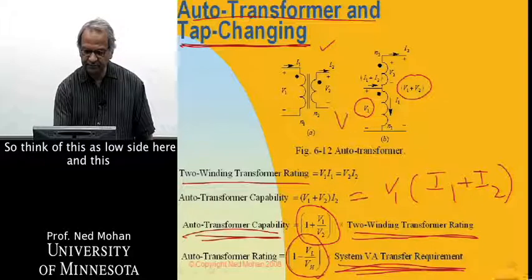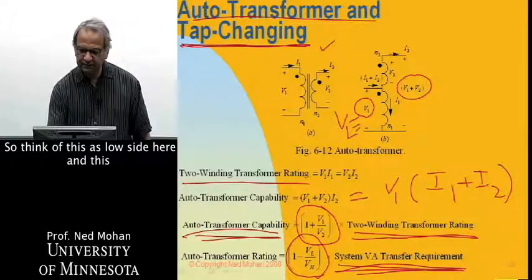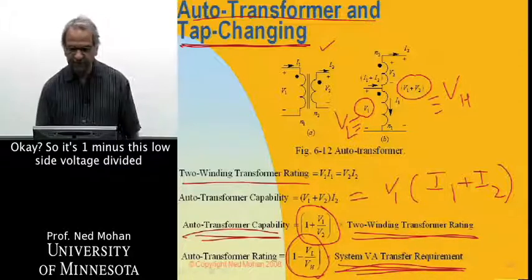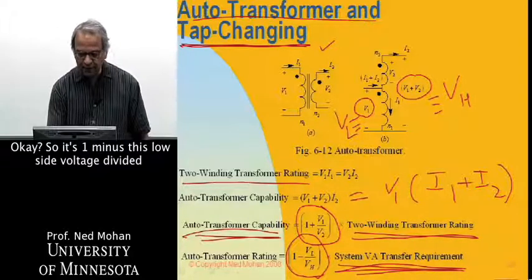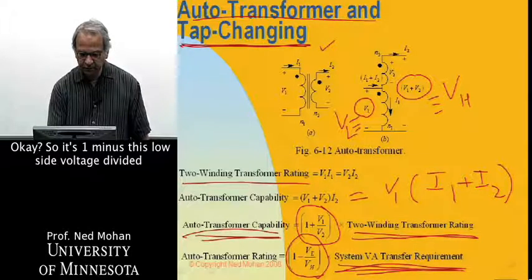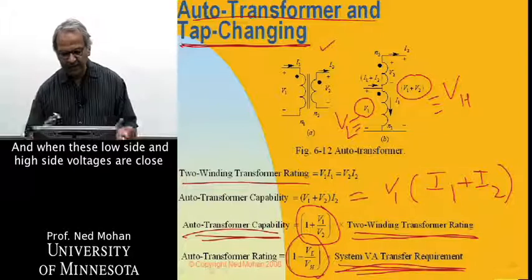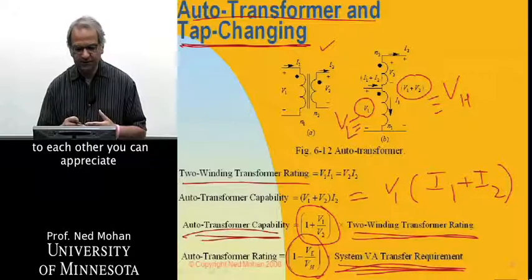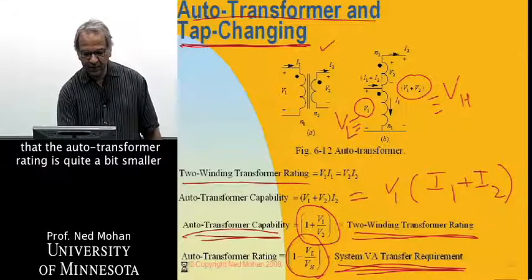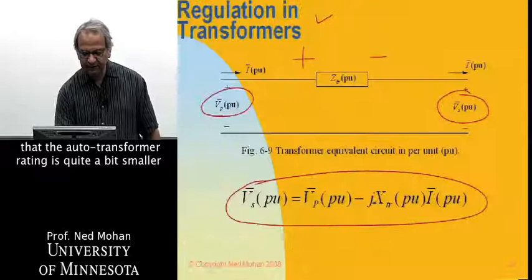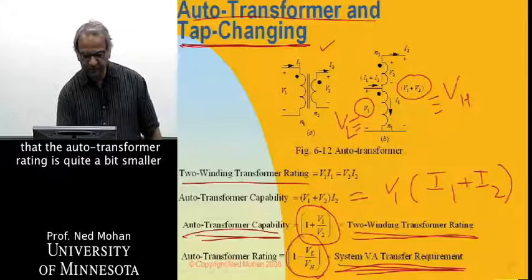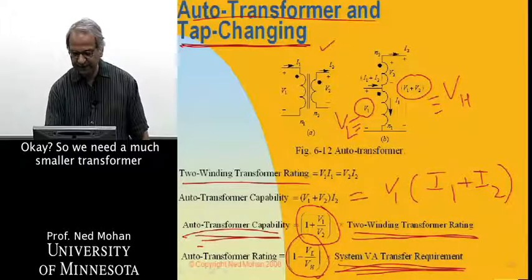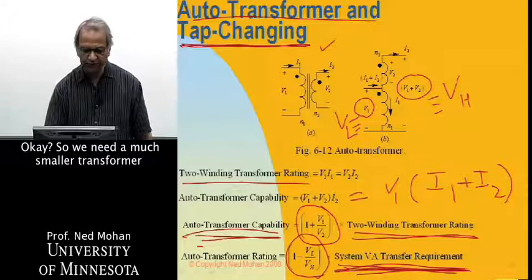So think of this as low side here, and this as the high side over here. So it's one minus this low side voltage divided by the high side voltage. And when these low side and high side voltages are close to each other, you can appreciate that the autotransformer rating is quite a bit smaller than the system VA transfer requirement.